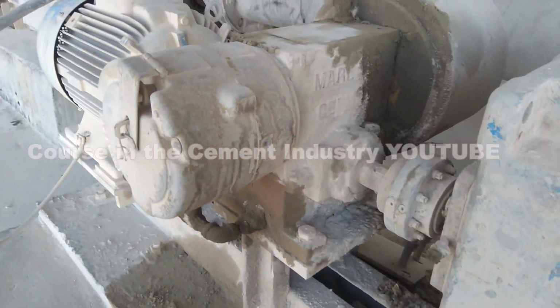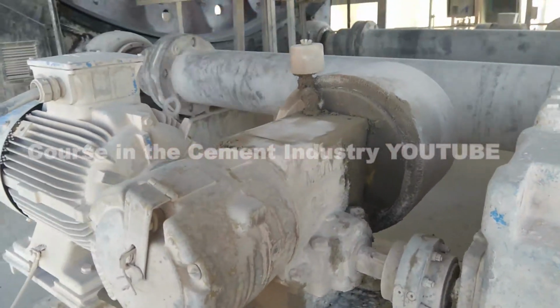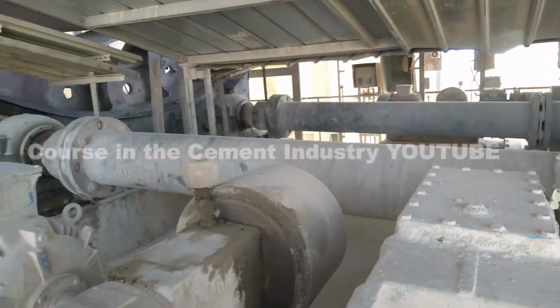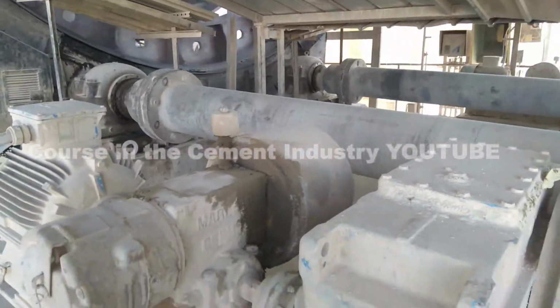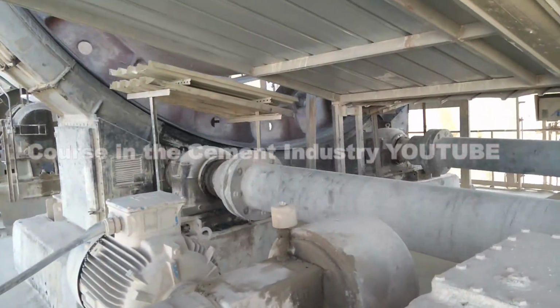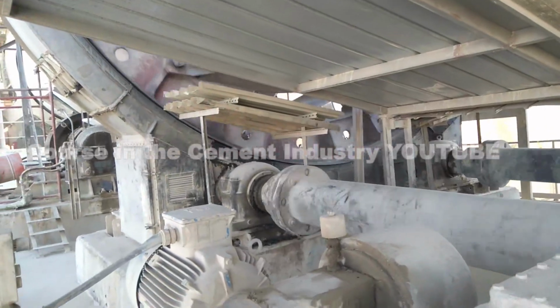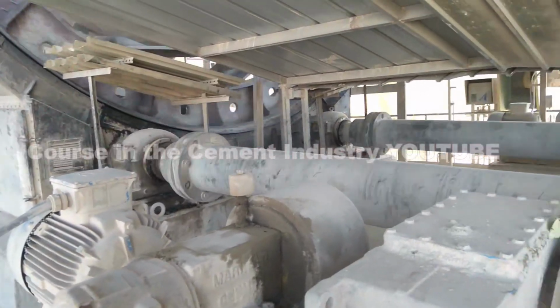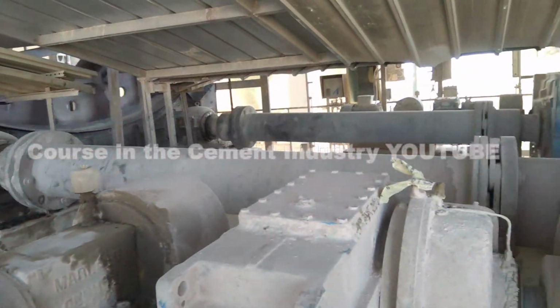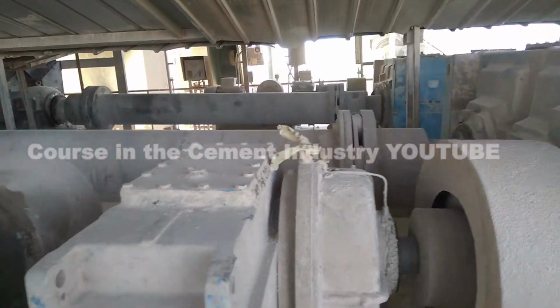Summary. Without a reliable main drive, the rotary kiln is useless. The most critical aspect for an operator or maintenance engineer is ensuring perfect alignment between the pinion and the girth gear, and maintaining a consistent spray lubrication system to prevent metal-on-metal wear.